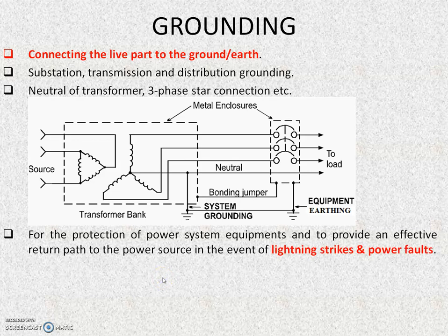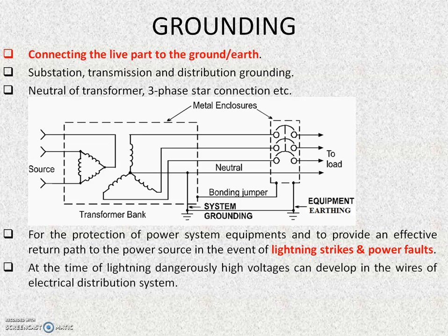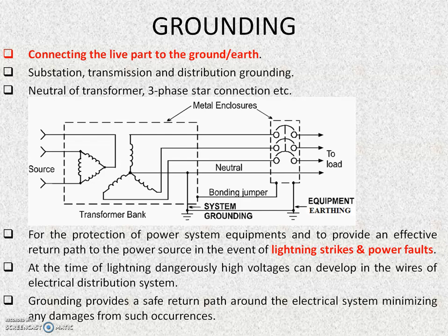It is for the protection of power system equipments and to provide an effective return path to current to the source in the event of lightning strikes and power faults. At the time of lightning, dangerously high voltages can develop in the wires of electrical distribution systems. So grounding provides a safe return path around the electrical system, minimizing any damages from such occurrences. So mainly it is for the protection of power system equipments. It is done at the system end, and so it is generally called system grounding or simply grounding.